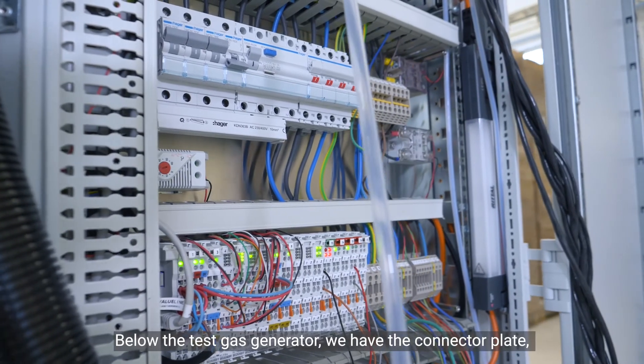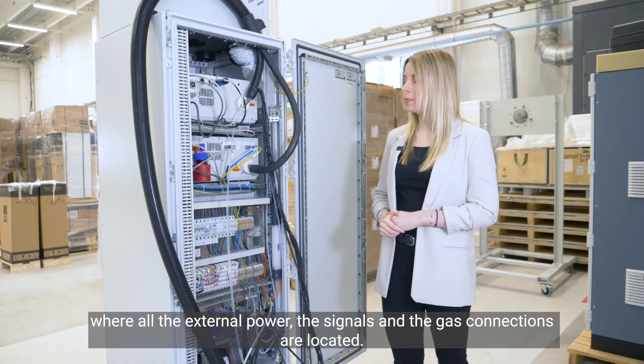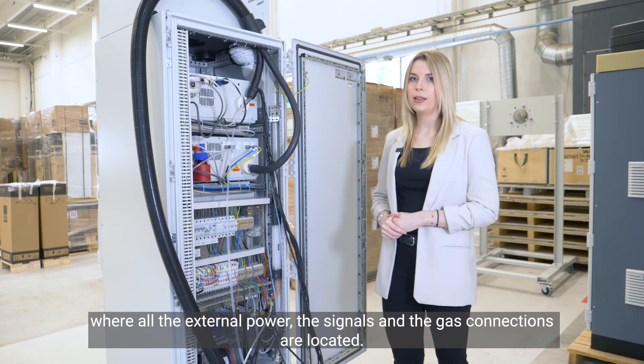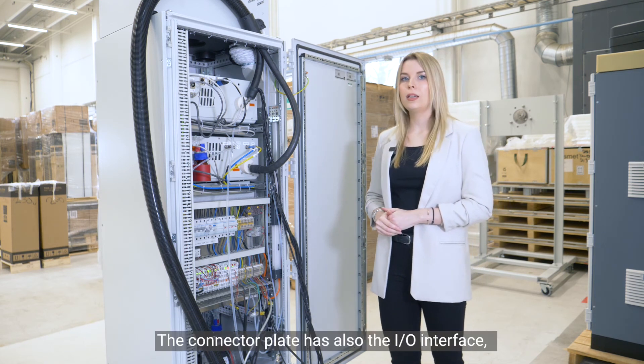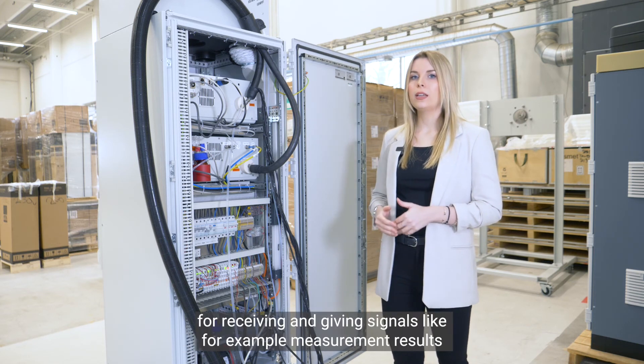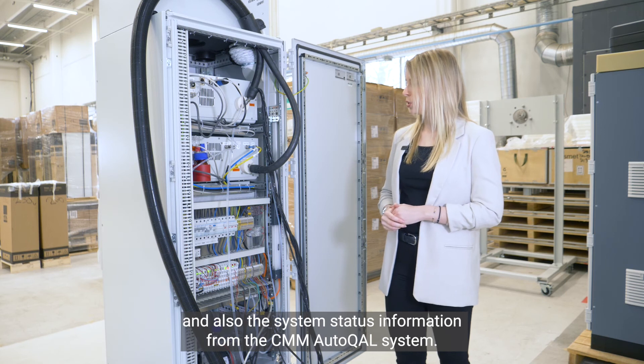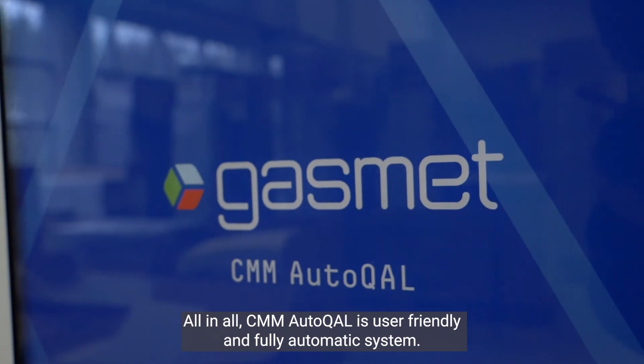Below the test gas generator we have the connector plate, where all the external power, signals, and gas connections are located. The connector plate also has an input/output interface for receiving and giving signals, such as the measurement results and the system status information from the CMM AutoQAL system.